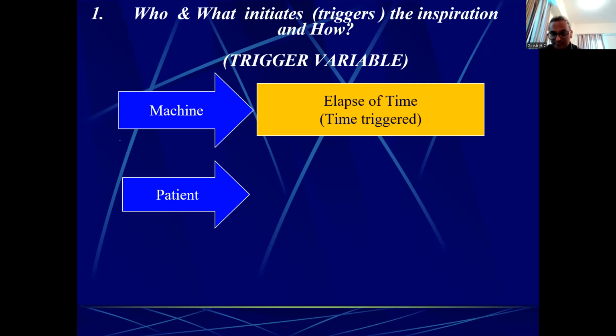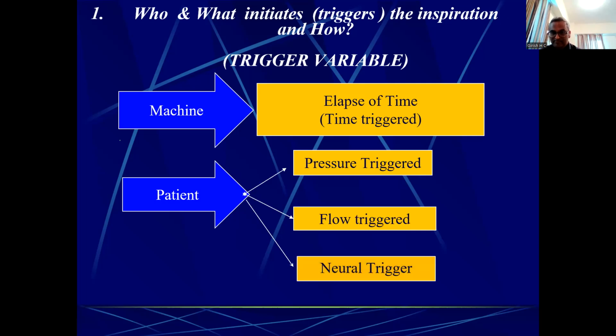Negative. Yes, that is what you were telling before. That is, either it is pressure triggering or flow triggering or neural trigger. We'll come to that, right? So what do you mean by pressure triggering? Some negative pressure generated is what they're saying. Correct. So when the patient begins to take a breath, there is a negative pressure generated in the circuit. Then the machine senses that pressure drop and gives a breath. That is called patient triggered, pressure triggered breath.